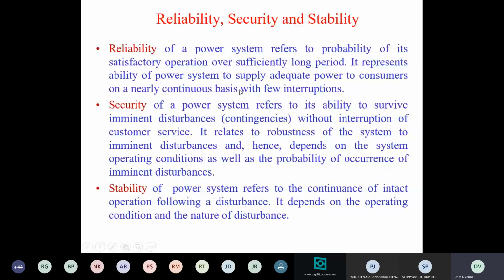Then security is the ability of our power system to survive imminent disturbances. It means even if you have vast disturbances or severe contingencies, under that condition also all the constraints are satisfied. So it relates to the robustness of the system following imminent disturbances. So if all constraints are satisfied, then security will also involve this. Dynamic security will also involve stability. So what is stability? Stability is continuance of intact operation following a disturbance. So following a disturbance, the system again settles to some equilibrium point. You get a certain intact operation point. But it may also have a periodic orbit. That is also the case of what is called marginal stability. So the ability to regain intact operation depends upon the nature of the stability.